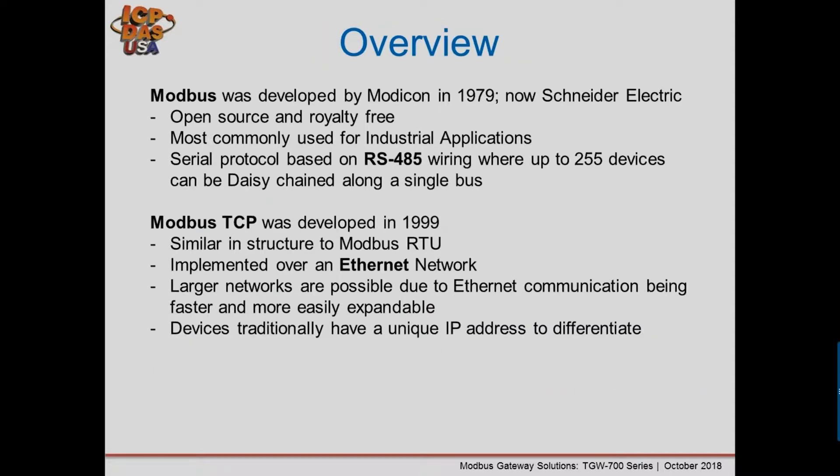Modbus RTU was developed by Modicon in 1979, now owned by Schneider Electric. It is open source and royalty-free, making it the most commonly used industrial serial protocol. It is usually implemented over RS-485, but can also be implemented over RS-232 or RS-422. Using RS-485, you can wire up to 255 devices along a single bus by daisy chaining modules.